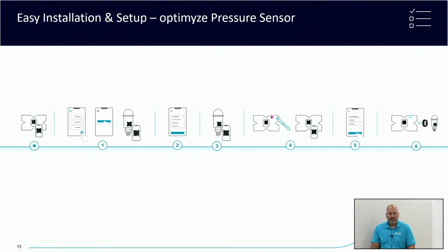And then lastly, some more pictorial instructions that would be sent with each pressure sensor. The first one there, that's the asterisk. That is just telling you that you need an Optimyze sensor in order to use the Bluetooth pressure sensor. You can't just use that Bluetooth pressure sensor by itself. It needs to communicate through the Optimyze sensor to get the data. Step one, on the main dashboard of the Optimyze sensor itself, there's a little plus sign in the bottom right corner. That's how you would add any Optimyze sensors or Bluetooth pressure sensors to the mobile application.